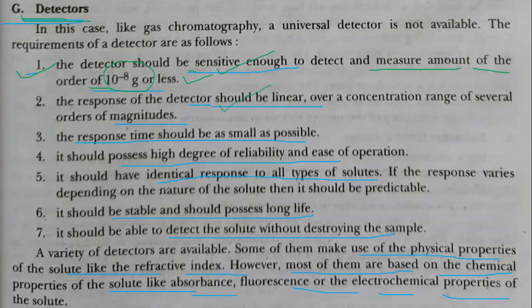It should give a linear response, and the response time should be very small, meaning it should give a quick response for each and every species that comes out of the column. It should have a high degree of reliability and should be easy to operate. It should have an identical response to all types of solute. And it should be stable and possess a long life. It should be able to detect solute without destroying the sample.